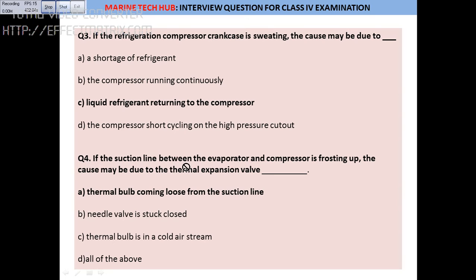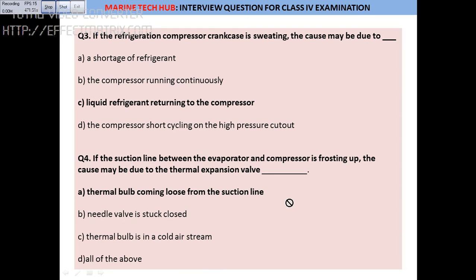Question 4: The suction line between the evaporator and the compressor is frosting up — what is the cause? Due to the thermal expansion valve, if there is frosting between these two components, the cause is the thermal bulb coming loose from the suction line. If the thermal bulb is loose and not sensing correctly, the expansion valve is not working properly, causing frosting on the line.